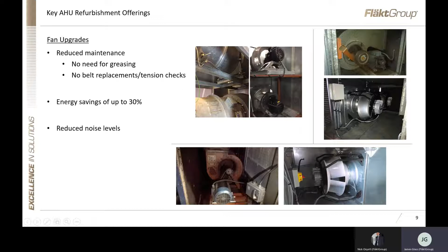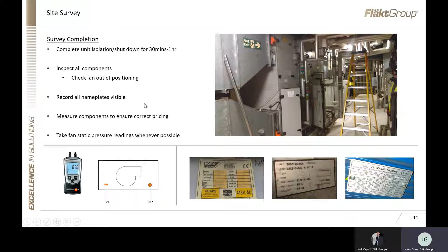The survey process takes about 30 minutes to an hour to complete. We go out and take note of all of the components within the air handling unit: the pressure development, the volume, the model number, the motor kilowatt rating. We look at all of the components within the unit, record it, and measure the fan chamber and other associated sections.